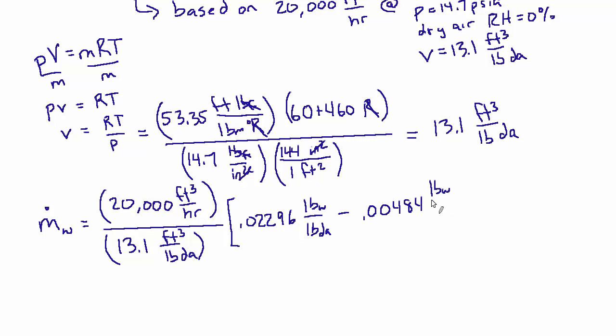And that works out to a mass flow rate of water of 27.66 pounds of water per hour, because the cubic feet cancel and the pounds of dry air cancel. So it ends up being pounds of water per hour, which is exactly what we want. And again, that is water that's been removed.